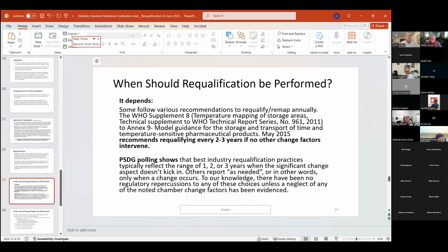Let's see, when should it be performed? And it depends, of course. Some follow various recommendations to requalify or remap annually. The WHO Supplement 8, temperature mapping of storage areas, a technical supplement to the WHO technical series, whose title is Model guidance for the storage and transport of time and temperature sensitive pharmaceutical products, issued in May 2015, recommends requalifying every 2 to 3 years if no other change factors intervene. The discussion group has taken some polls on this because we're all over the lot on it, but they show that the best industry requalification practices typically reflect the range of 1, 2, or 3 years when the significant change aspect doesn't kick in.